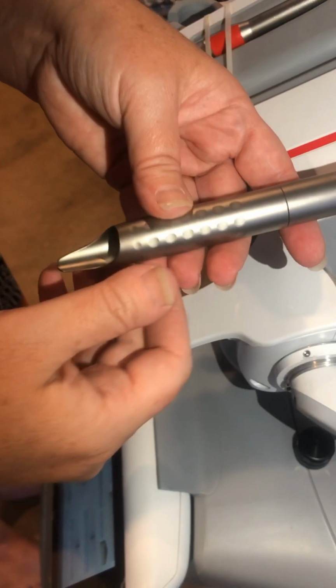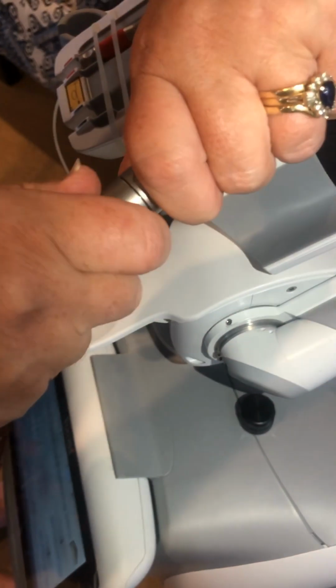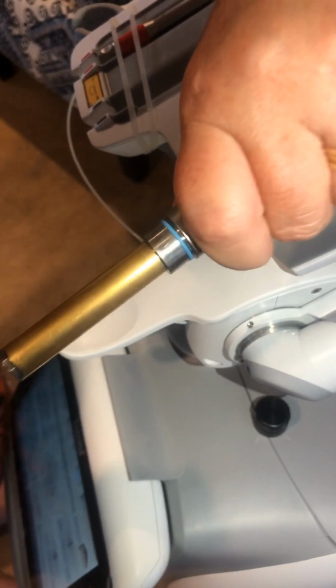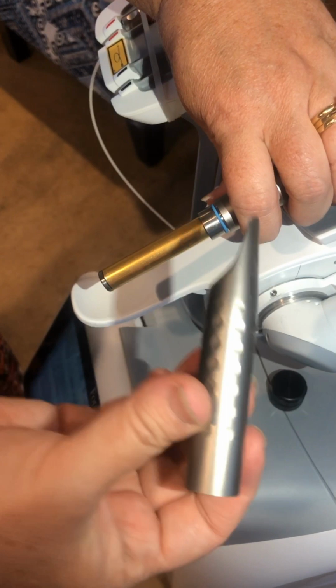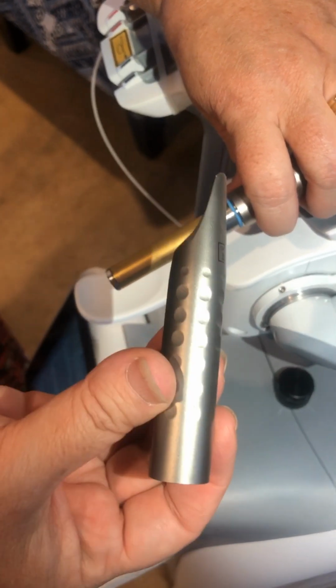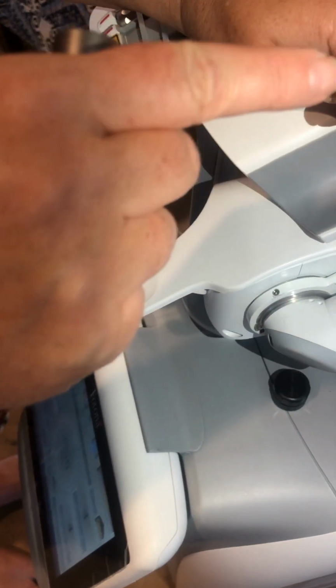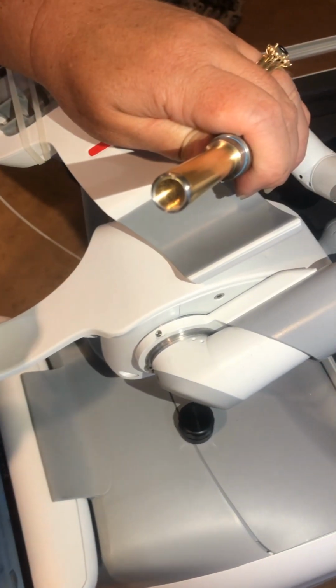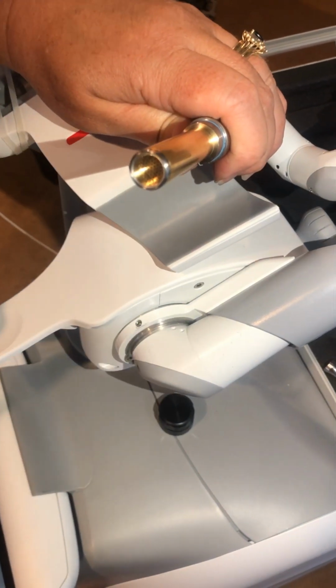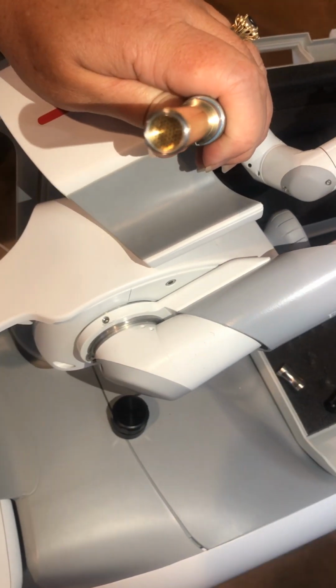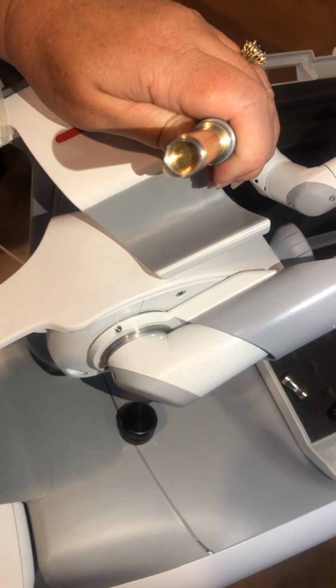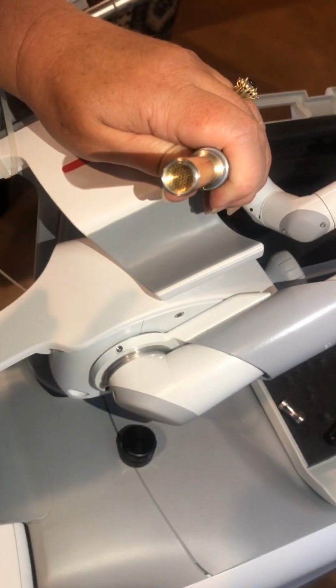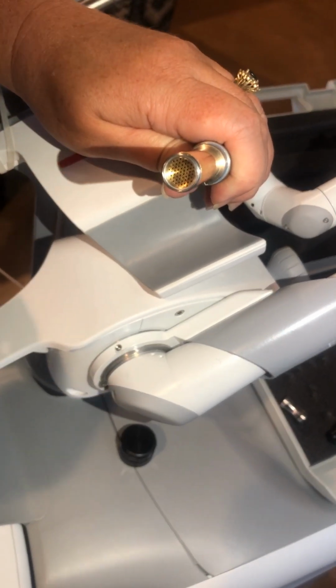The only piece on this that is actually able to go through sterilization: if you pull straight at the end, this part will come off. This part can go through sterilization. It's the only piece of the handpiece that can. You have a lens here on the end of that, which you want to check for fingerprints or debris. That should always be nice and clear. If it's not, we're going to use 100% acetone or 70% alcohol on a Q-tip to clean that off.